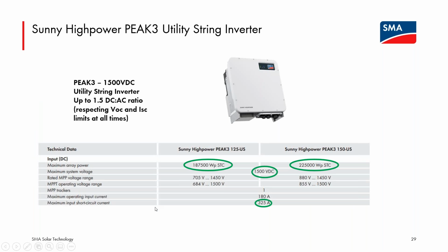footprint. In this slide, we're showing kind of the same thing we did for the CORE1, the top part of the data sheet for the two variants, the power classes for the PEAK3. There is the open circuit voltage limit for all of these units, which is now 1500 volts DC. And there is a short circuit current limit, but as there is one input on the DC side, there is only one number here, and it is quite large, 325 amps. Of note, that is the short circuit current limit for the inverter. In operation, the inverter will draw a maximum of 180 amps from the array attached to it.